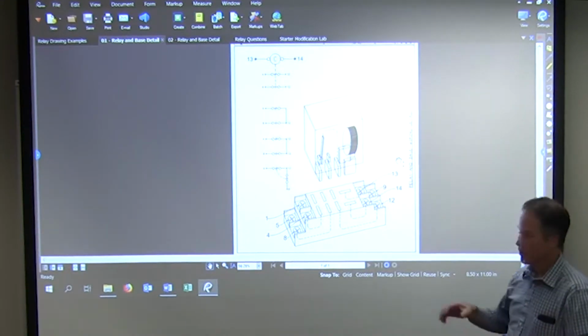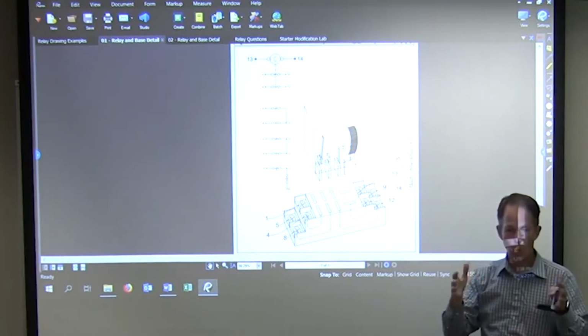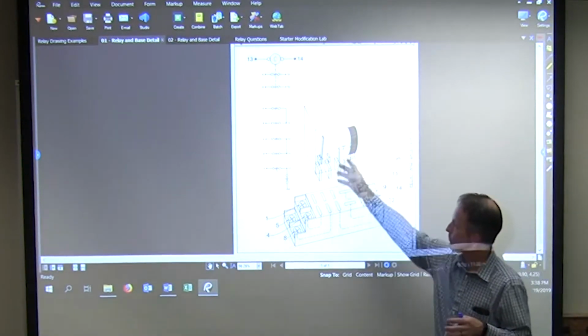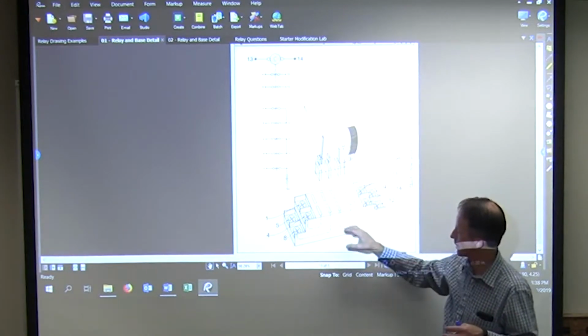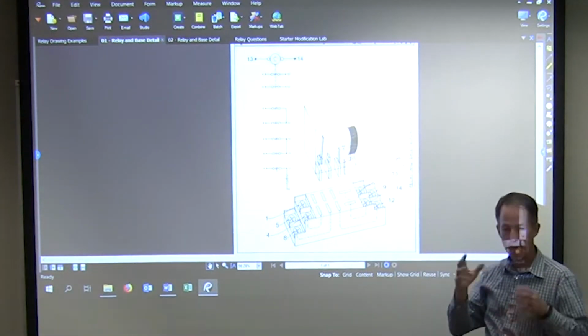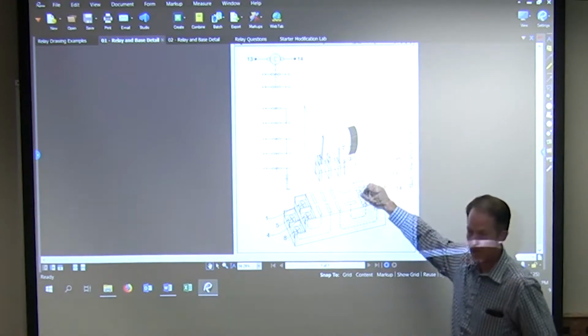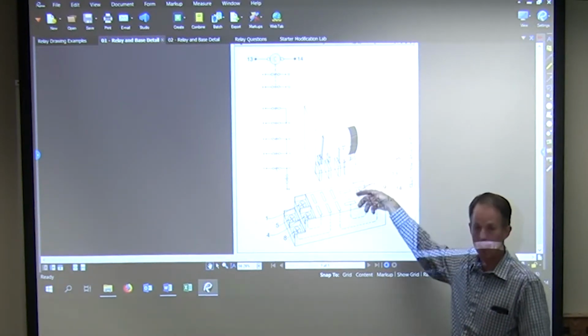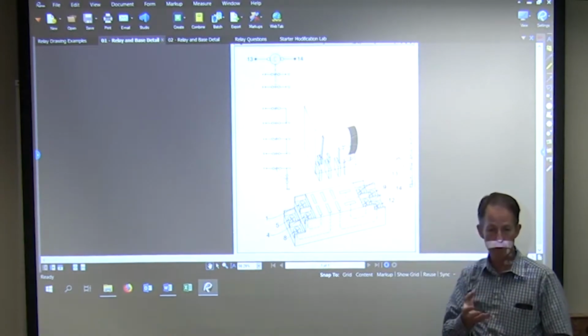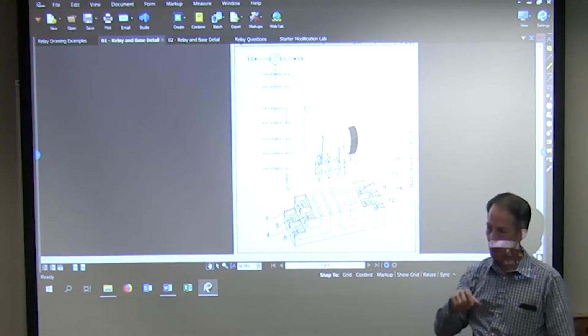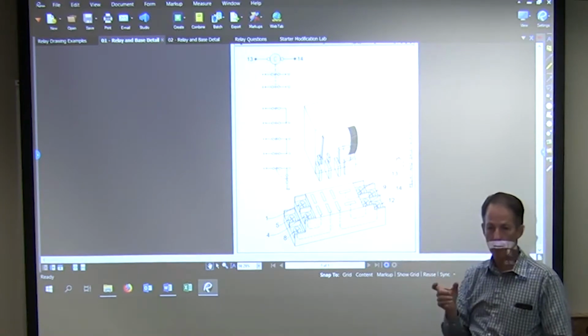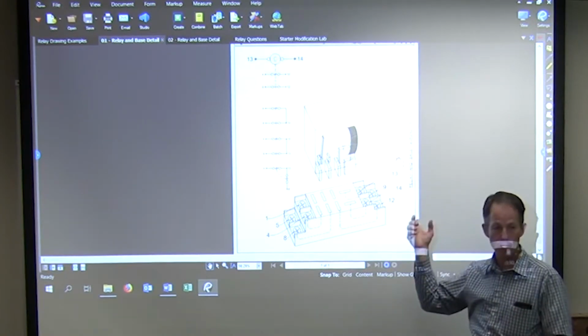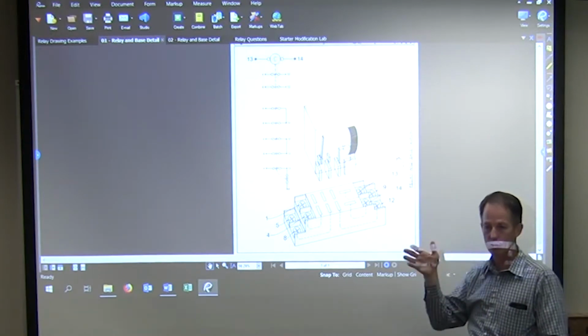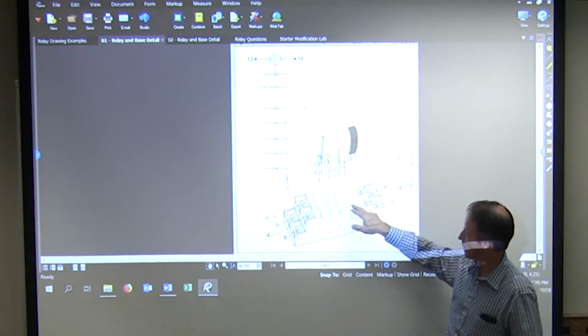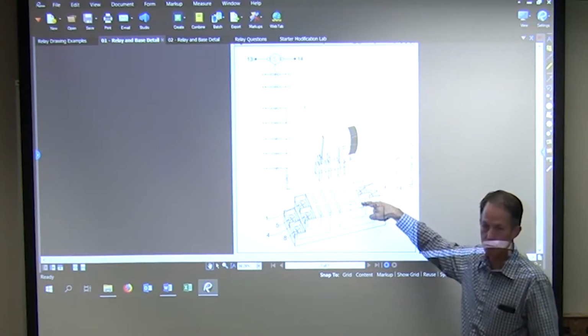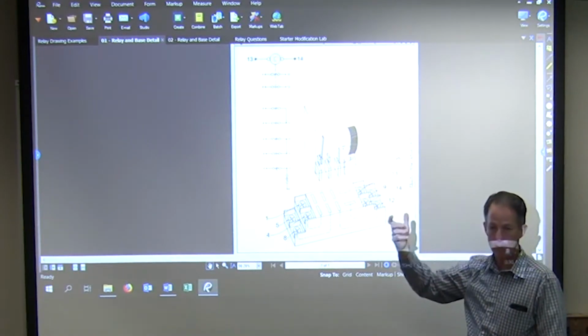Okay. So on these bases, they oriented the tabs on the relay that will plug into the socket. They orient the tabs to help us identify what's what. The two by themselves that are perpendicular to the others are the coil. That's where we're going to apply the 120 or 24 volts, or if it's DC, we'll apply that voltage to make this relay switch from one set of contacts to another. Typically, those will be off of these top two screws if you're using our standard base type relays.